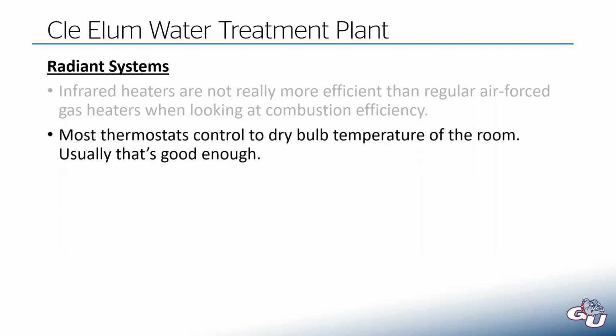Which I need to do another quick side digression on. Well, why would we use these then? Most thermostats control their heating systems to maintain some dry bulb temperature of the room. So if you want your room at 70 degrees Fahrenheit, that heater will cycle on and off as needed to keep the room at 70 degrees dry bulb temperature. And for your basic HVAC system, that's fine. 99% of HVAC systems, that's all they're doing.